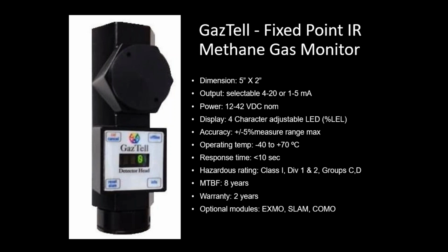The mean time between failures, the MTBF, on all our GazTell series is 8 years, and that's electronics. Basically, the unit itself with the electronics are all rated for at least 8 years. We've found with the determinator, we have many units out there that are approaching, I'd say, between 12 and 15 years old that are still operating very well. But just be aware that calculated MTBF is 8 years. And of course, when you start going to other sensors, you have to look at the sensors that are plugged into the electronics to actually get the longevity of a specific gas detector head.